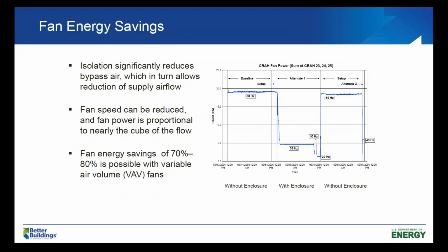So what we did was we put in a temporary barrier. It was an experiment. We realized that we only slowed the fans down from 100% to basically 2/3, but because of the cube law relation between flow and power, we saved 3/4 of the fan energy and fully met the cooling needs of the equipment. Next slide.